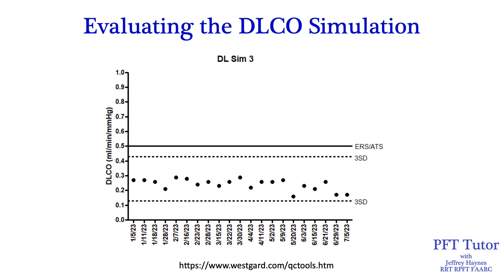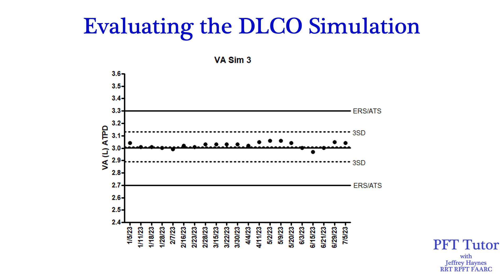I plot the DLCO simulation data in a Levy-Jennings plot, like you'd use for blood gas quality control data. I also set a 3 standard deviation limit, which tends to be tighter than the ERS ATS limits. I use my statistical software to make these graphs, but there are plenty of videos on YouTube showing how to do this in Excel. You can also do this for free on the Westgard website — go to tools and you should see the tool there; I'll place the link in the description. I also plot the simulated alveolar volume in a Levy-Jennings plot, and adding a 3 standard deviation range is, in my opinion, a better way to set the simulation limits — much tighter than the ERS ATS limits.